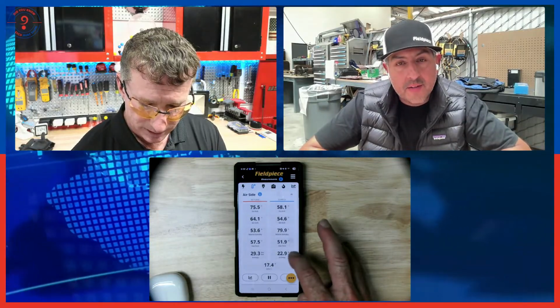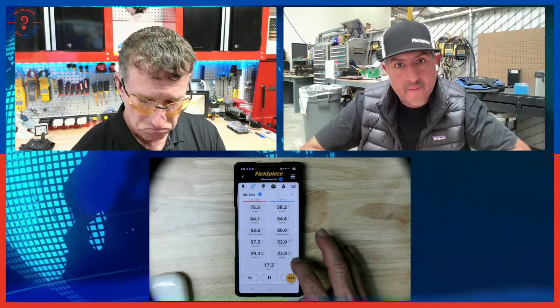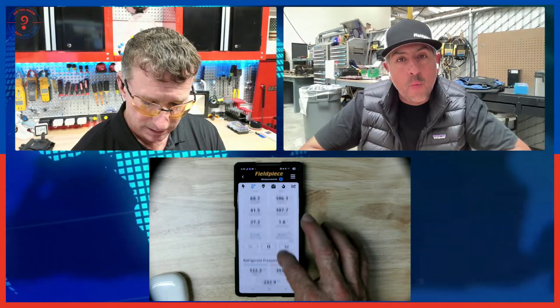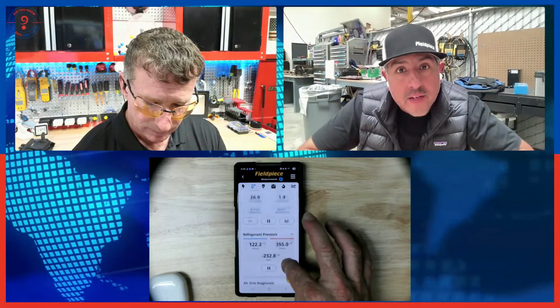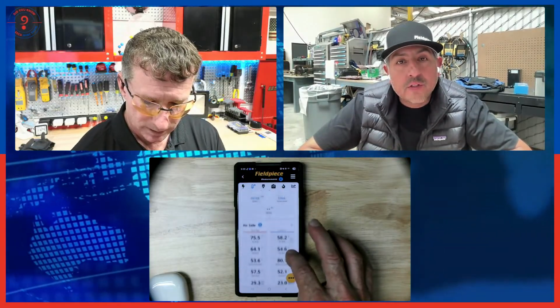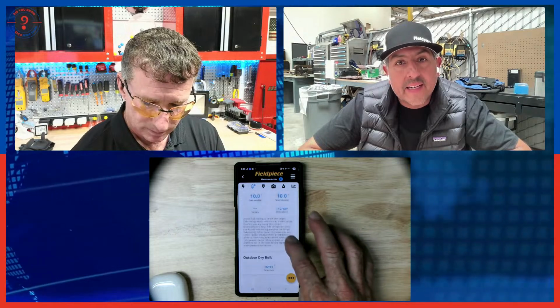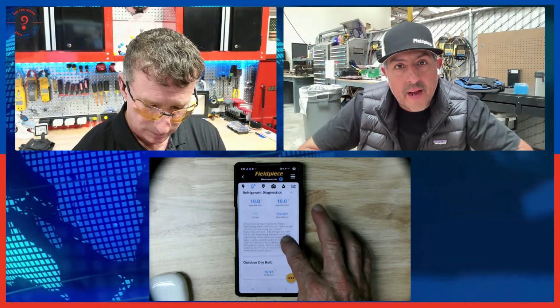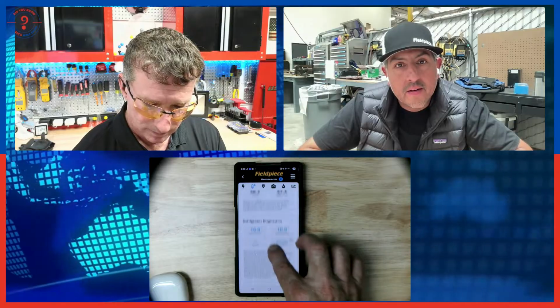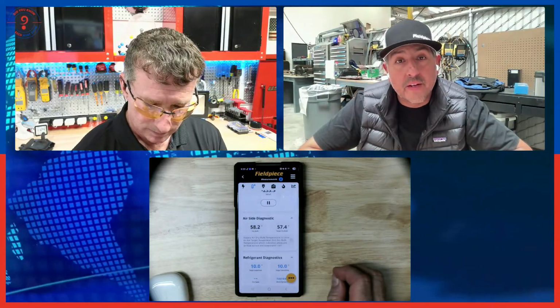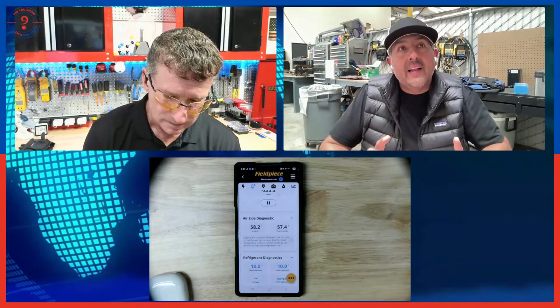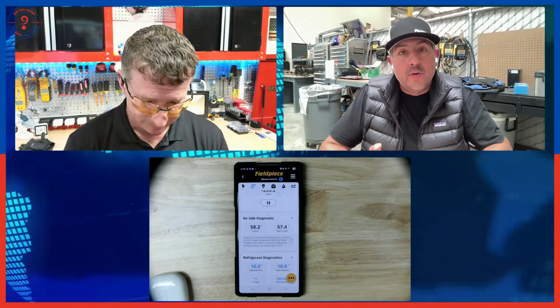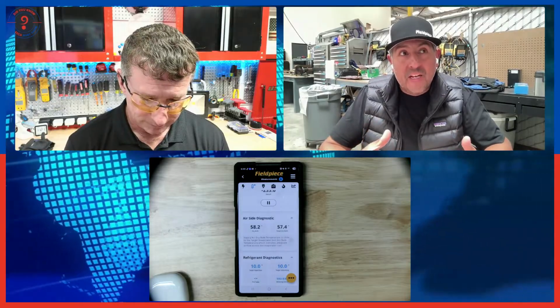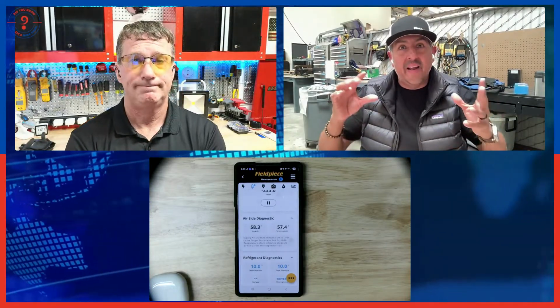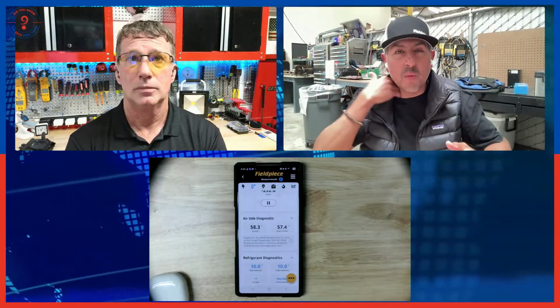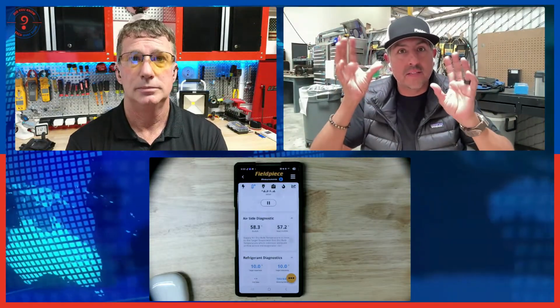It looks like our delta T was about 17 degrees. Okay, if you scroll down to the bottom, do you have the airside diagnostics turned on? A little bit higher. Okay, airside diagnostics, perfect. When we look at the air at the indoor unit, one of the measures that we use is delta T. As an industry rule of thumb, we're looking for about 18 to 20 delta T.